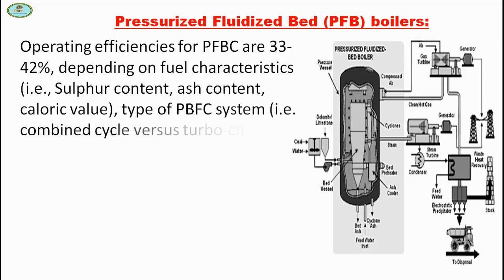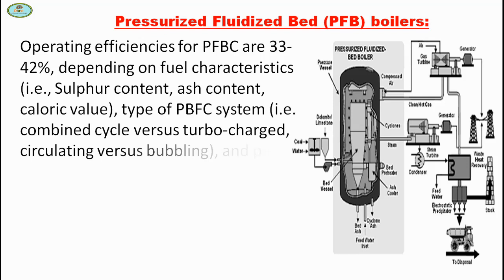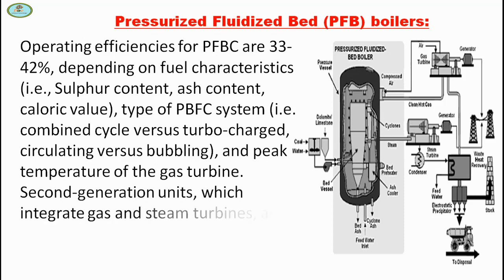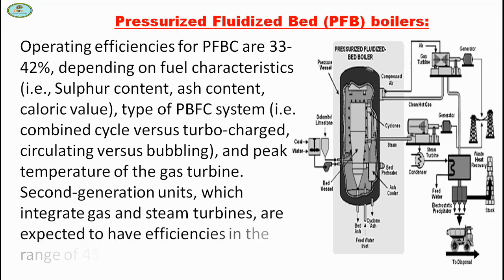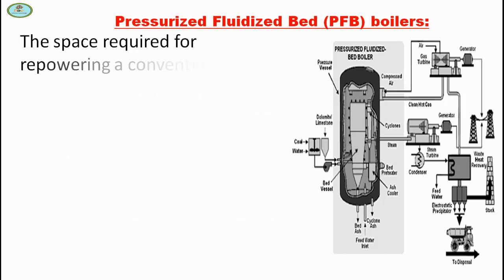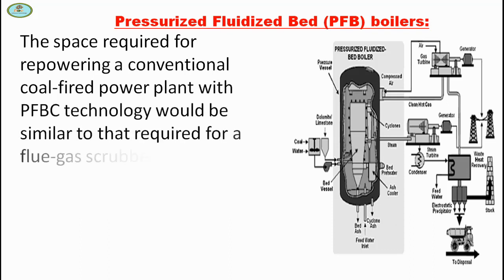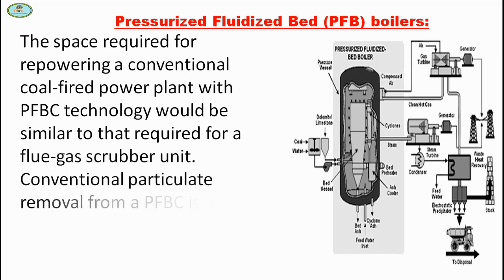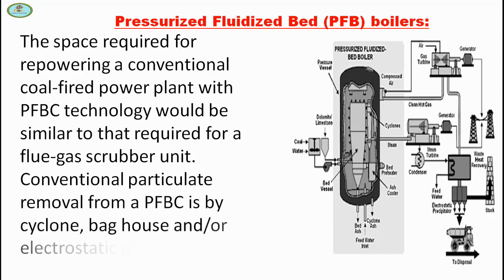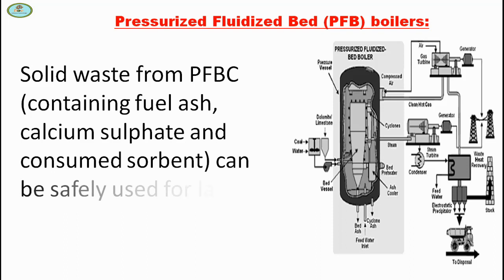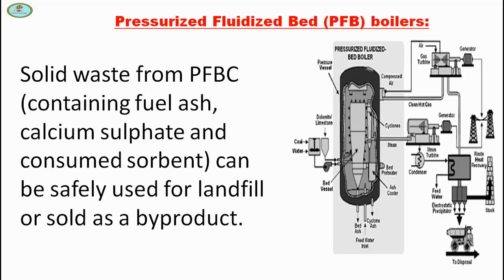Types of PFBC systems include combined cycle versus turbocharged, circulating versus bubbling, and peak temperature of the gas turbine. Second-generation units, which integrate gas and steam turbines, are expected to have efficiencies in the range of 45 to 50%. The space required for repowering a conventional coal-fired power plant with PFBC technology would be similar to that required for a flue gas scrubber unit. Conventional particulate removal from PFBC is by cyclone, bag house, and electrostatic precipitator. Solid waste from PFBC containing fuel ash, calcium sulphate, and consumed sorbent can be safely used for landfill or sold as a by-product.